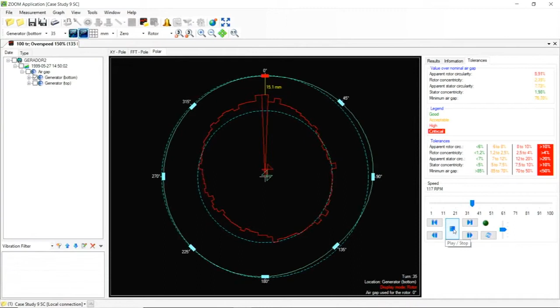As the unit slows down, we're down to 99 RPM here, and you can see it's still floating—values still high. Now it's starting to improve. Technically, the unit has gone back to a shrink fit, within the acceptable range. But again, the speed shows it's 5 RPM below nominal, and 14 RPM below design. So it functioned basically the way it was designed to—it just did not do so at the correct speed.